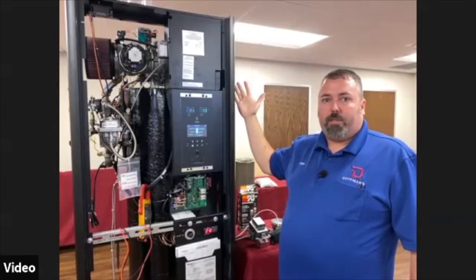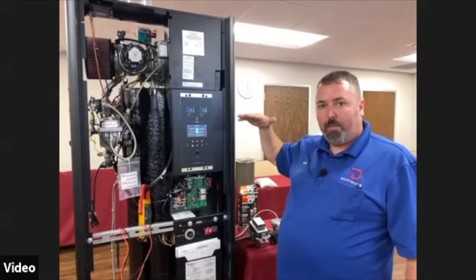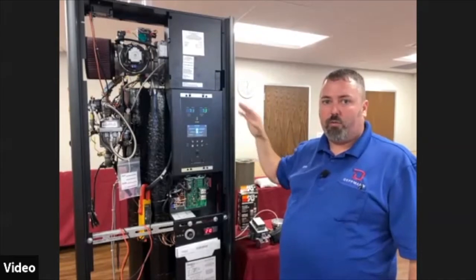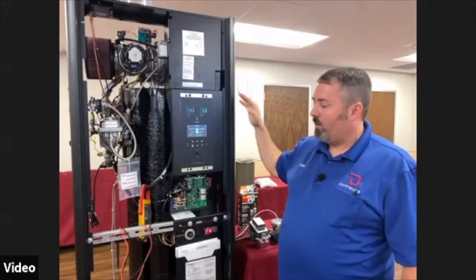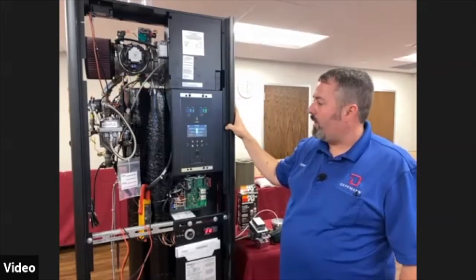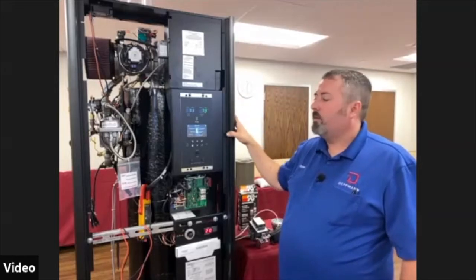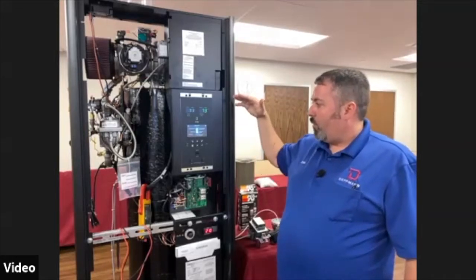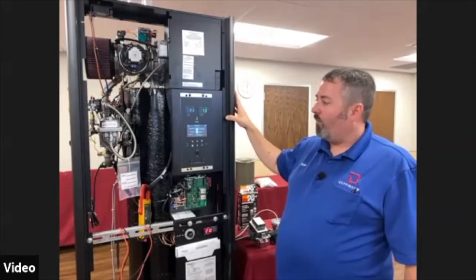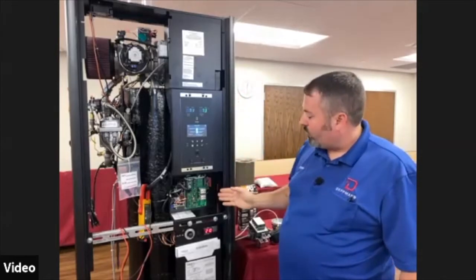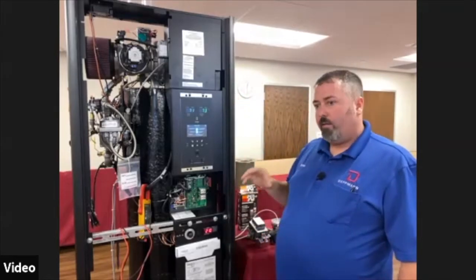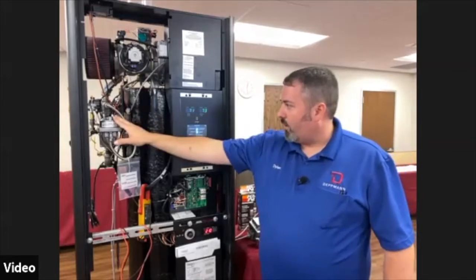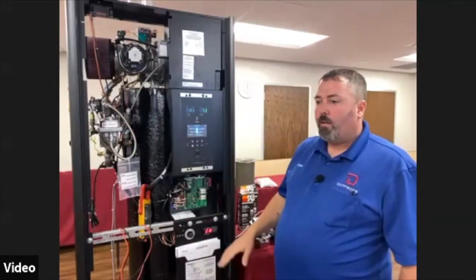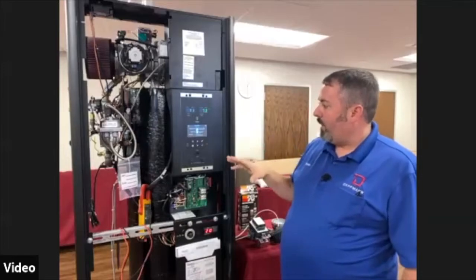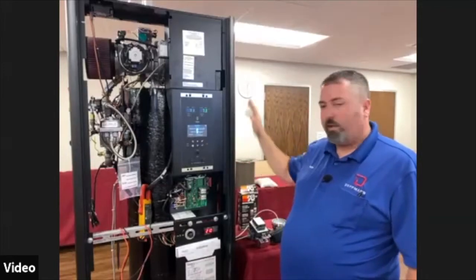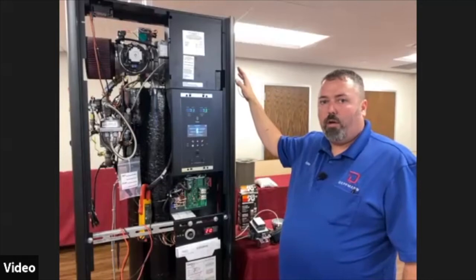And then once the loop is up to temperature, the boiler will start ramping down to keep the boiler running and maintain the proper heat load. So we like these to stay running for as long as possible, just nice even heat. However, if you do reach your set point or slightly go over it, the boiler will shut down, the heat demand will drop, and then the SSOV will shut, the flame will go out, and the boiler will go into its standby position. At that point, you may notice that the blower is still running.